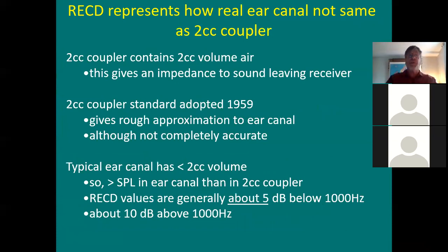Real ear to coupler difference represents how the real ear canal is not the same as a 2cc coupler. A 2cc coupler contains 2cc volume of air. It was adopted in 1959. It gives a rough approximation to the ear canal, but not 100% accurate. The typical ear canal has less than 2cc volume. The differences are generally about 5 dB below 1,000 Hertz and about 10 dB above 1,000 Hertz.